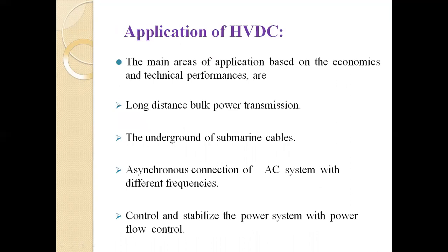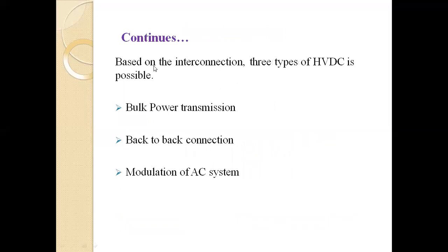So what are the applications of the HVDC link? The main areas of application, based on economics and technical performance, are, first, long distance bulk power transmission, which means we can transmit a heavy amount of power from one end to another end. Second, underground or submarine cables. For submarine cables, we can use the HVDC transmission line. Third, asynchronous connection of AC systems with different frequencies. We can connect two systems of different frequencies by using an HVDC link. Last, control and stabilization of the power system with power flow control. We can control the power flow and stabilize the power.